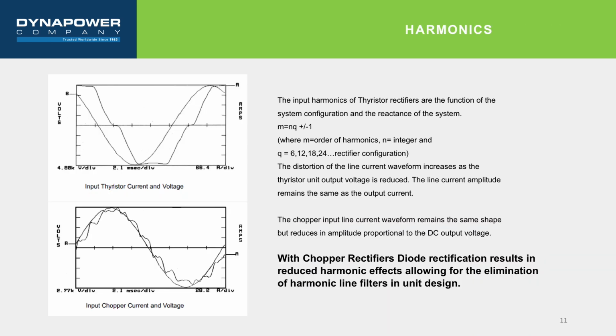In a thyristor-based rectifier, high harmonics are generated by the phase-controlled firing of the thyristors. Since the line current for thyristor-based supplies is typically rich in low-frequency harmonics, to meet harmonic control standards some harmonic compensation techniques, passive or active, have to be employed. As the input AC line conditions change, the tuning of line harmonic traps changes as well. This practice requires the application of a harmonic study in the early phases of the project.